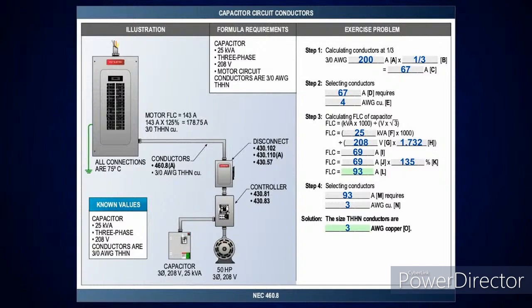Okay. Now, the other way I look at this is I can do it based on the full load current of the capacitor. Well, I've got a 25 kVA capacitor, which will give me 25,000 VA there, but it's a 208 volt 3-phase. So 208 volts times 1.732 will be 360 volts. You'll divide that into the 25,000. That's going to give you 69 amps. And then you go look at 460.8(A), it tells you to take that at 135%. So I take the 69 amps at 135%, that's going to give me 93 amps. And the next size above that in table 310.16 is 100 amps, which is a number 3 conductor. Well, based on those two calculations, the number 3 is larger than number 4. So therefore, the size copper conductors required are number 3. Okay.